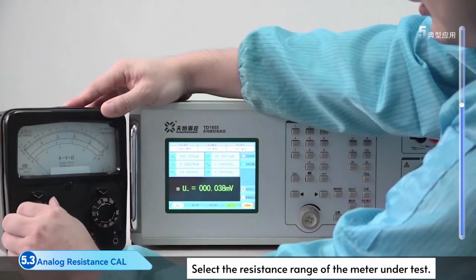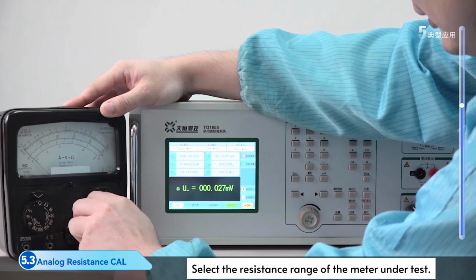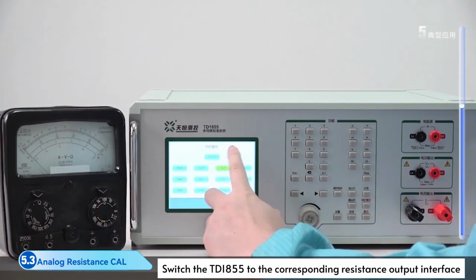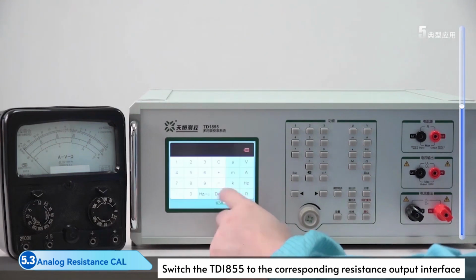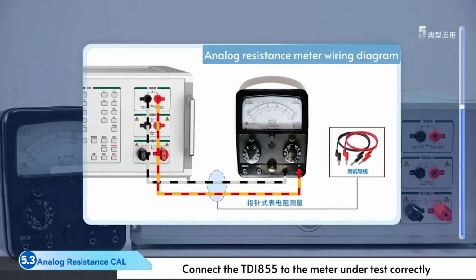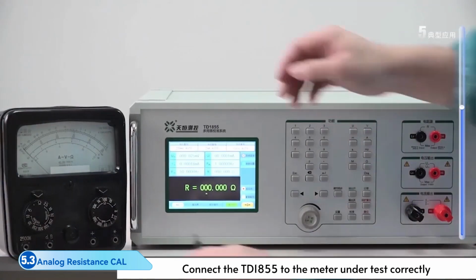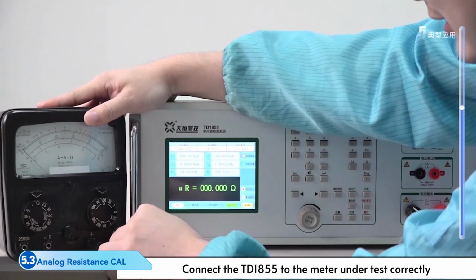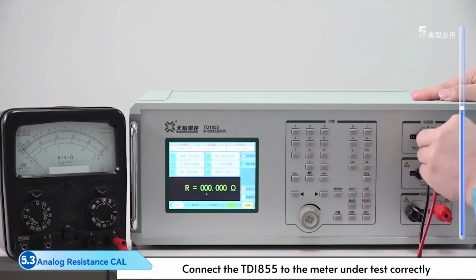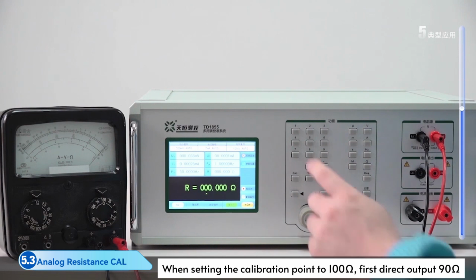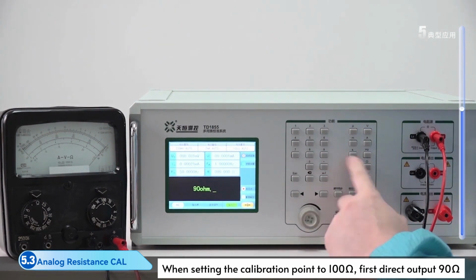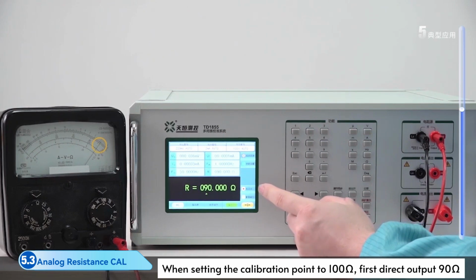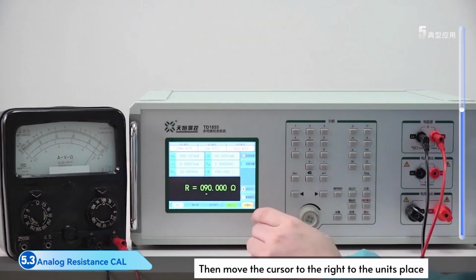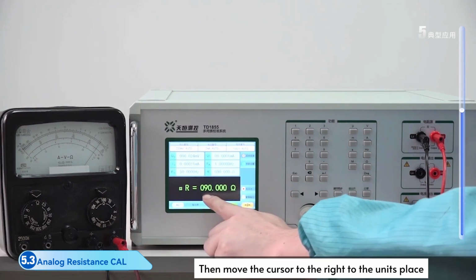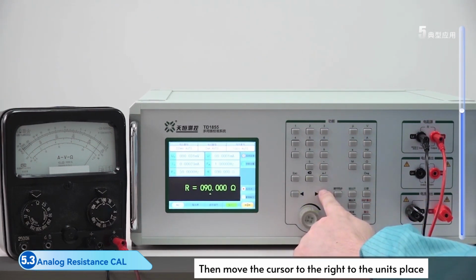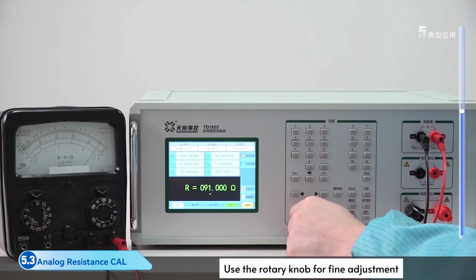Select the resistance range of the meter under test. Switch the TD1855 to the corresponding resistance output interface. Connect the TD1855 to the meter under test correctly. When setting the calibration point to 100 ohms, first direct output 90 ohms. Then move the cursor to the right to the unit's place. Use the rotary knob for fine adjustment.